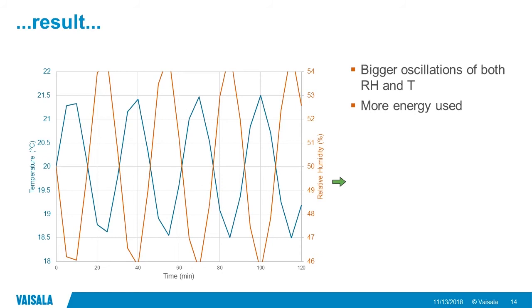So by trying to control very tightly, using relative humidity and temperature as control parameters, you're actually causing a lot of havoc in the HVAC system. You're trying to cool and heat and humidify and dry almost all the time. Right. So how can you fix this situation?